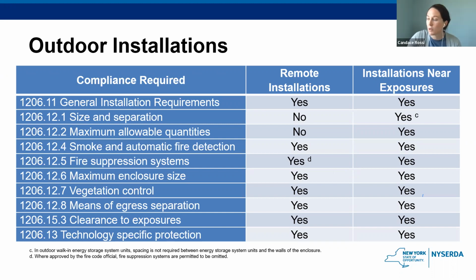So while it is a requirement for remote installations, basically, if the applicant can prove to the fire code official that this is not a requirement or their project shouldn't be subject to it, you are allowed to omit them. And you can also see for remote systems that size and separation is not a requirement, and the maximum allowable quantities is not a requirement either. And once again, this is based on the fact that they're further away and don't have as great of a risk to life and human health. So, and yes, we'll continue.